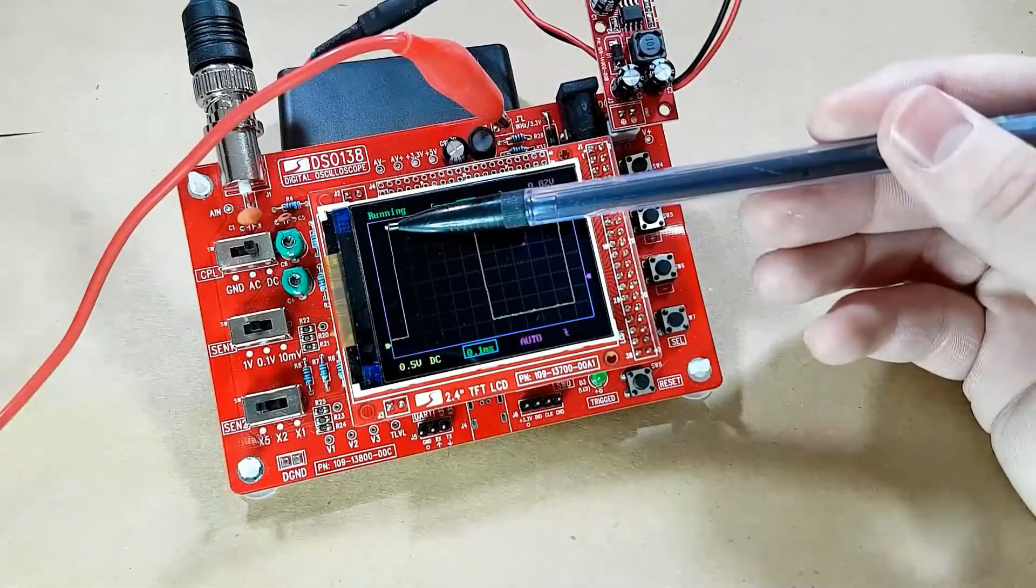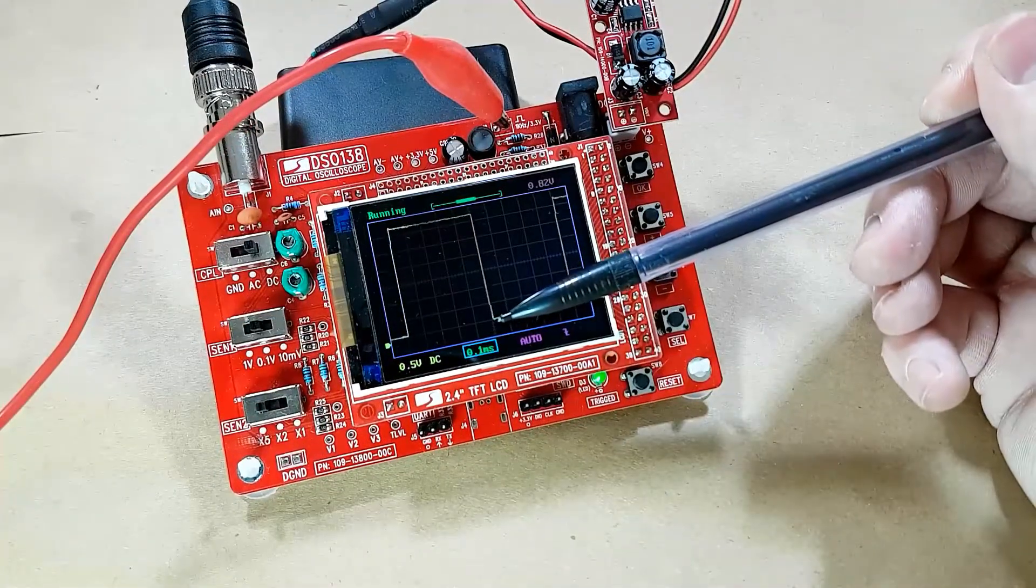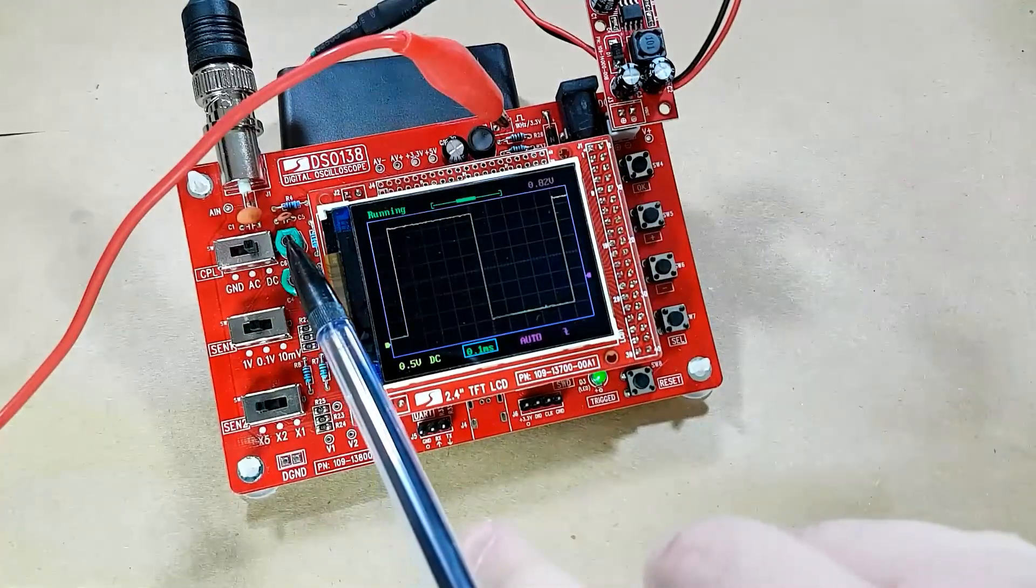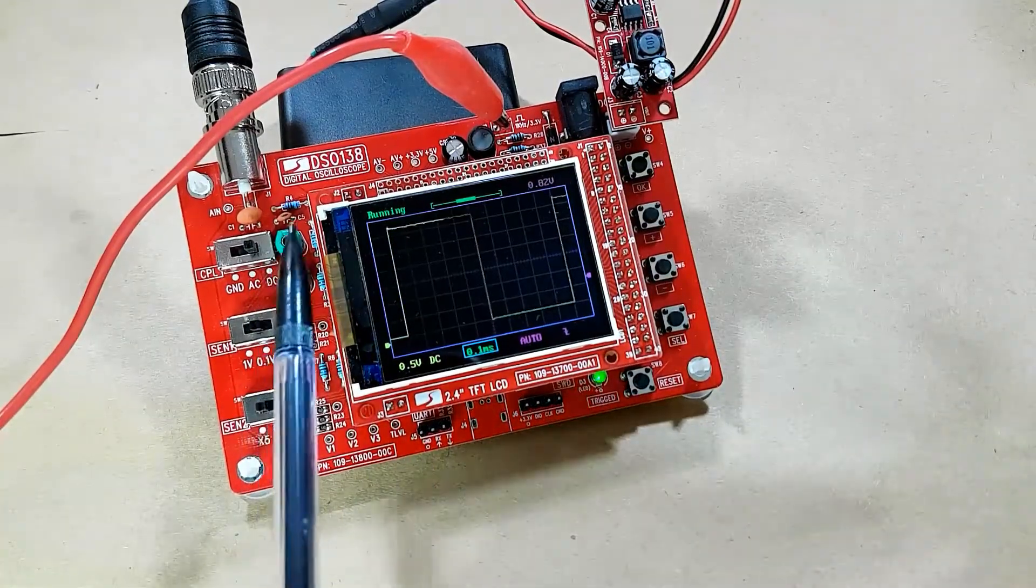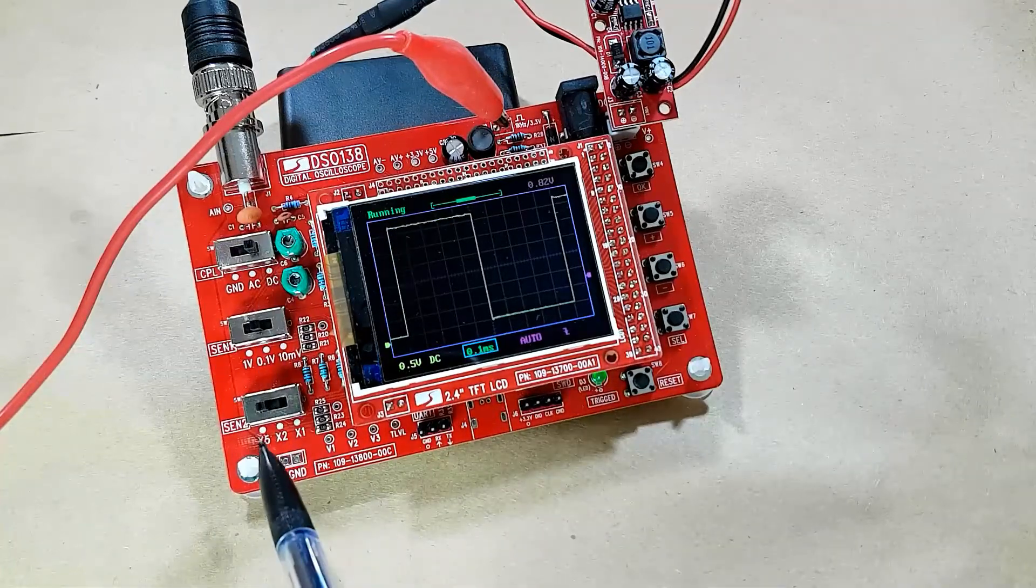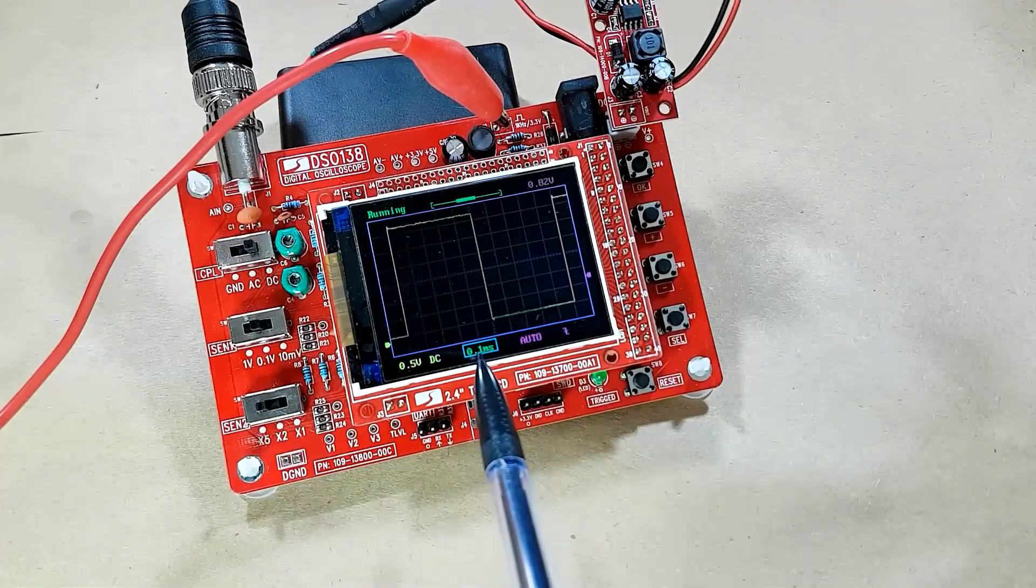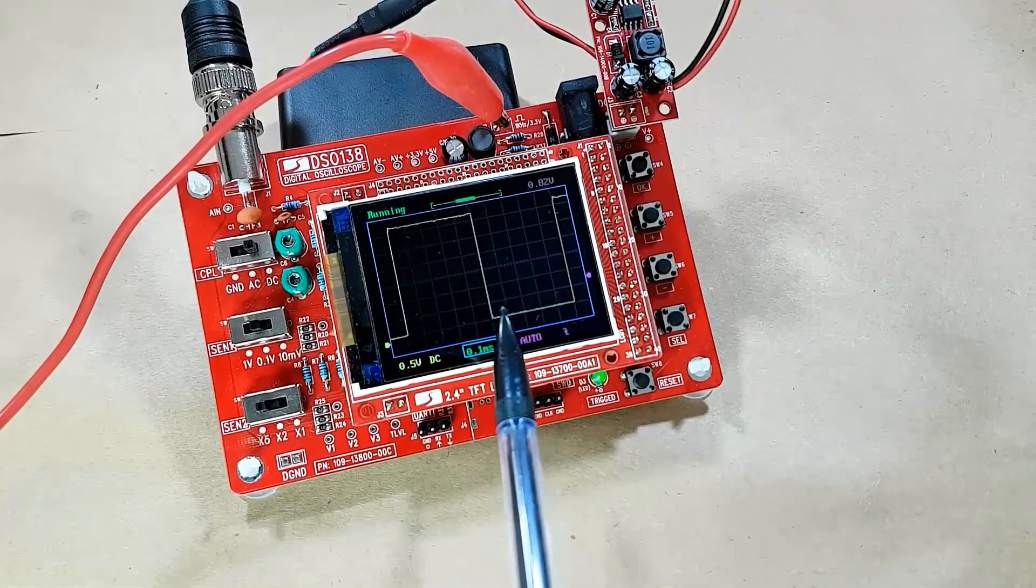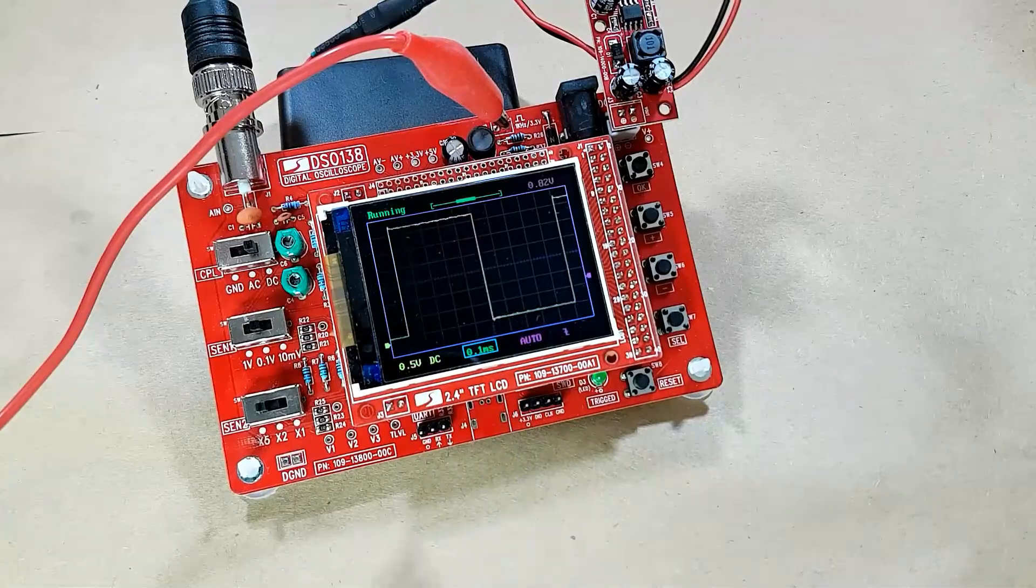There's not a whole ton of overshoot and undershoot, but if you do have big spikes, this is where these adjustable capacitors come into play. You set it to DC 0.1 volts, five times multiplier, then a time base of 0.1 or 0.2 milliseconds, and then you adjust those capacitors until you have a fairly smooth, level waveform.